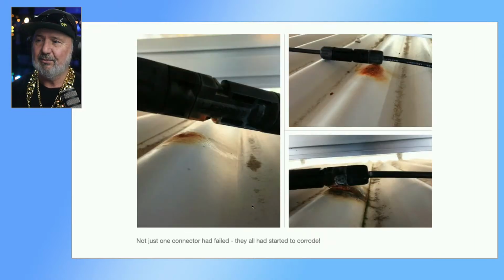So the issue really was not just a single point of failure, it was multiple points of failure. So that tells me it's not just a one-off accident. In fact, all the plugs showed some signs of rust, and of course these are live DC. Now remember, the inverter is transformerless, so if you connect the positive or the negative of a PV array and you have a transformerless inverter, you're going to get reverse fault current flowing from the grid side through that inverter. Yes, ouchie, ouchie, says Ray, indeed.